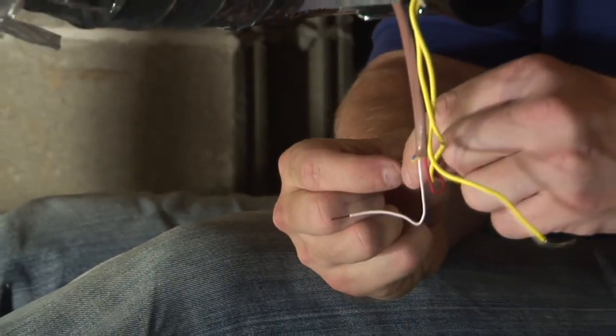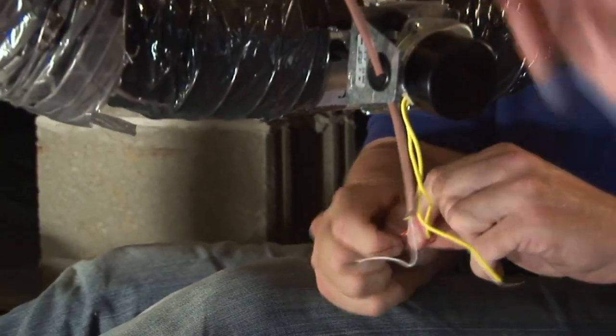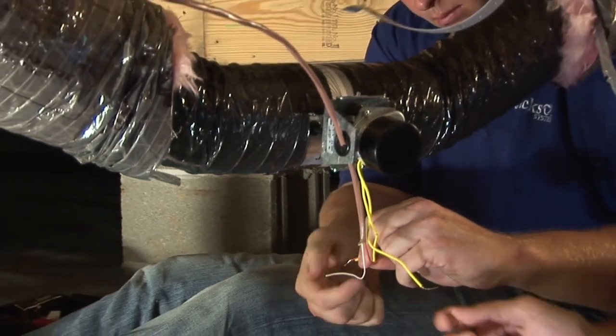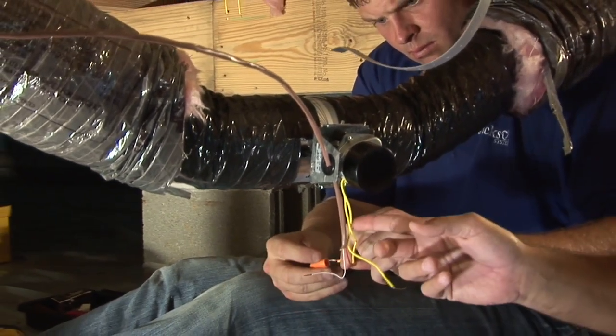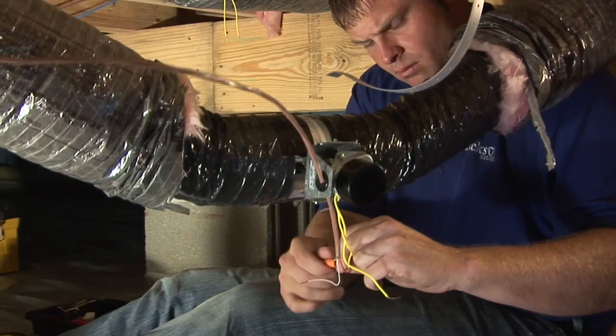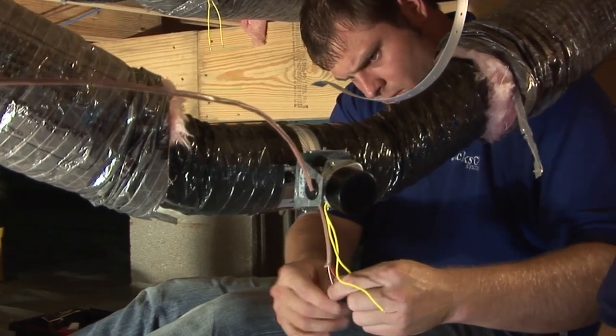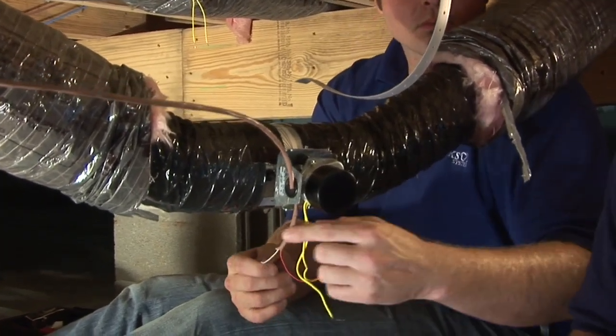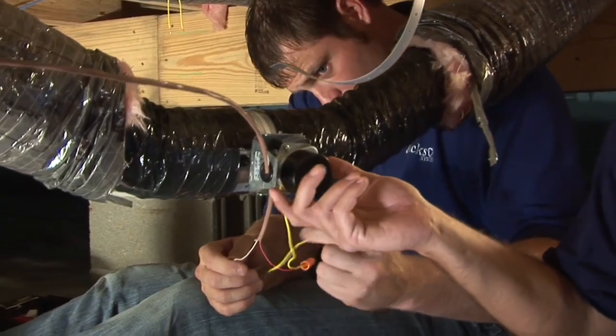What Ryan is working on right now is he has taken his thermostat wire here, 18 gauge thermostat wire, and run it to the zone damper. And what he's going to do here is make his connections to the 2-wire zone damper actuator. The actuator itself is not polarity sensitive, so it doesn't really matter which wire is which, and that'll matter most when we land it to the panel.